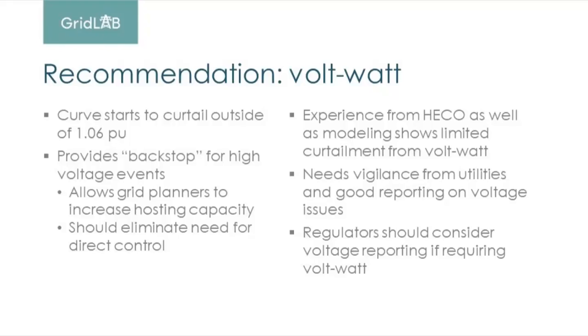But why are we recommending volt-watt? We really think it provides a backstop for high voltage events. It gives comfort to utility planners that they're able to increase the hosting capacity of these circuits and get more DERs on them, knowing that they have this backstop. If something goes wrong, because the circuit gets reconfigured, some load drops off or some DER trips off and increases the voltage, these devices are going to autonomously do what's necessary to bring the voltage back into line. And we think it also eliminates the need for direct control, because a lot of utilities think, well, the only way I can be certain about the voltage of these DERs is if I have control over the devices.